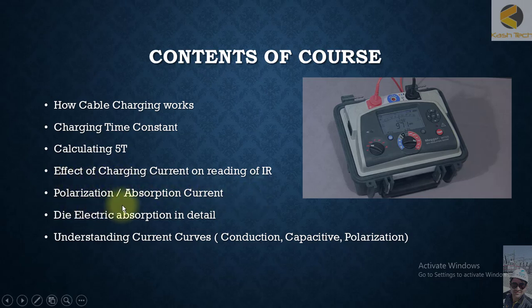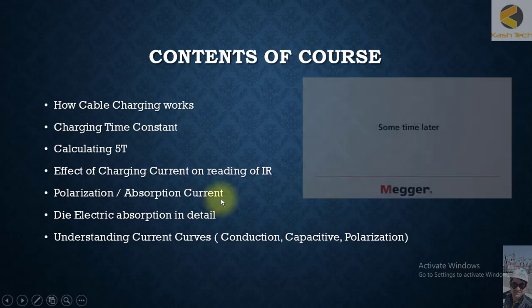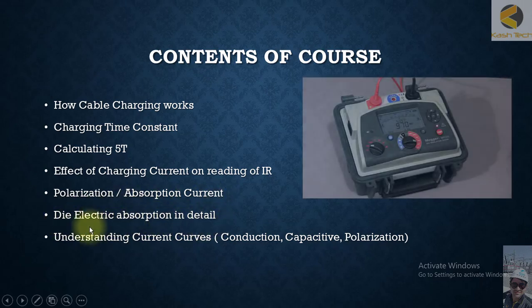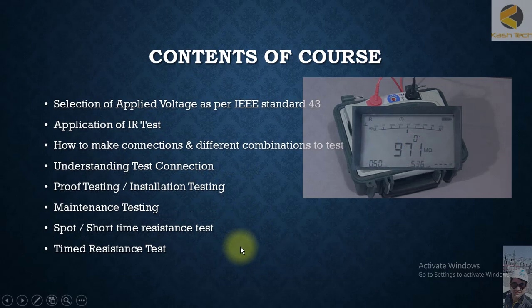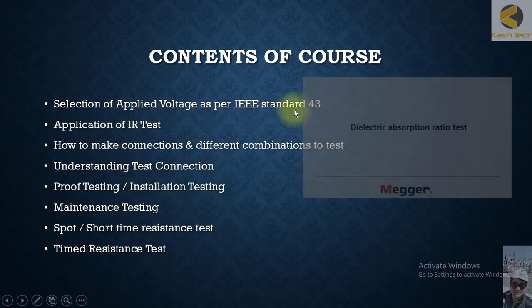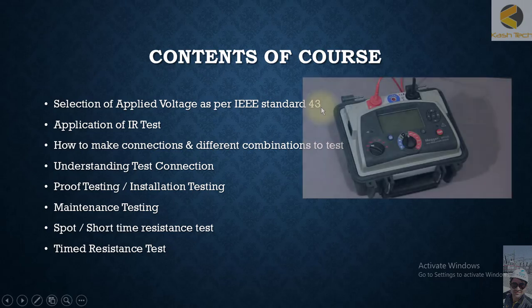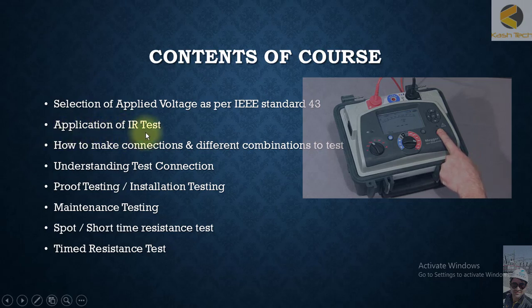We will discuss the effect of charging current on the reading, polarization or absorption current, and dielectric absorption in detail. We will show a curve illustrating conduction current, capacitive current, and polarization current — surface leakage current is included in the conduction current. We will also cover selection of applied voltages as per IEEE standard 43, with a table showing which voltage to apply based on the insulation voltage rating.